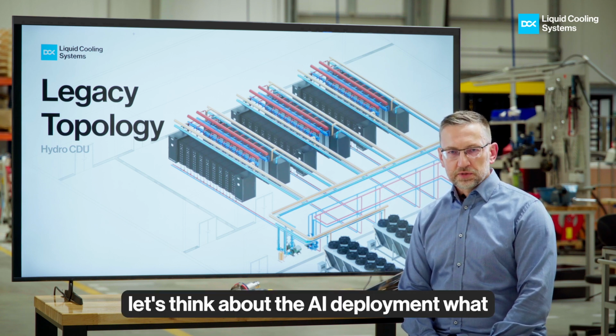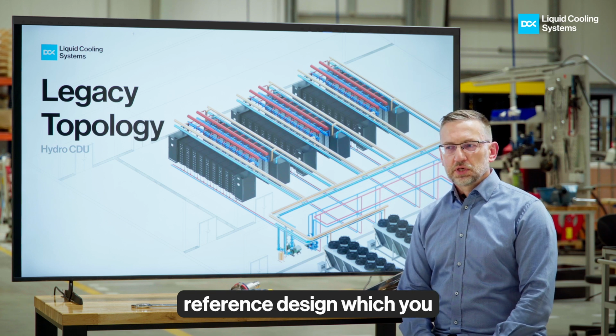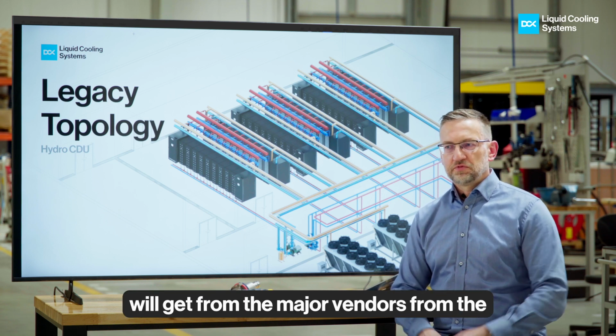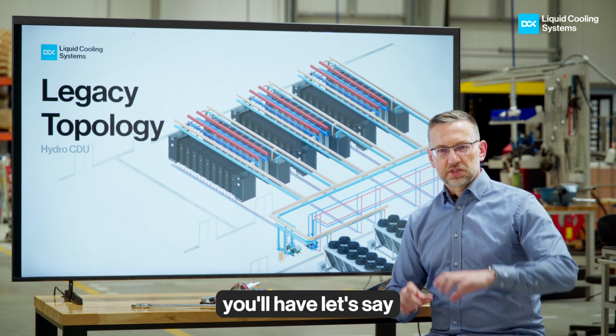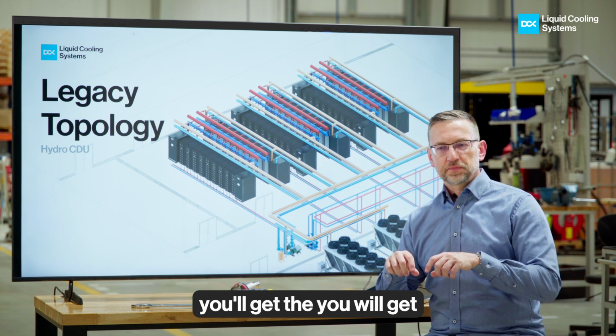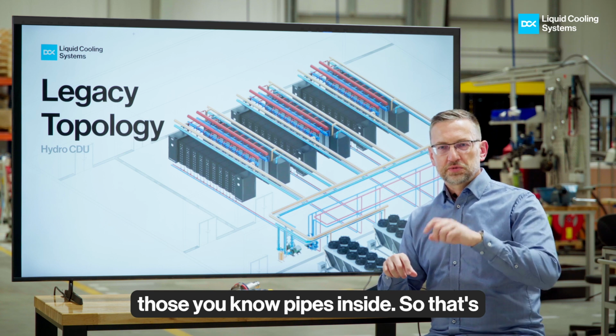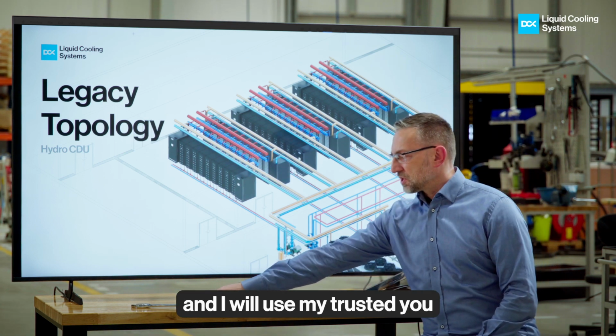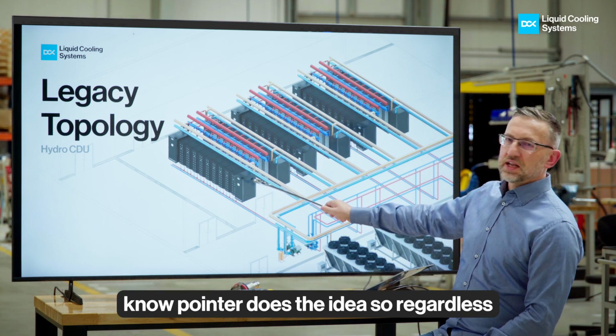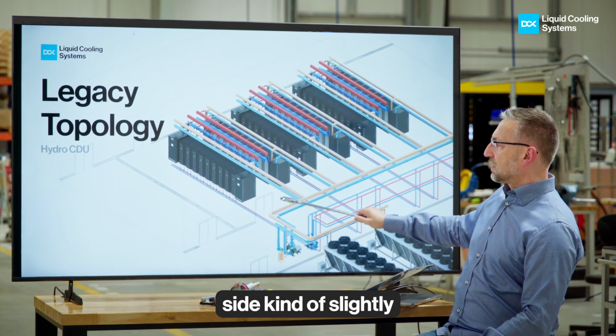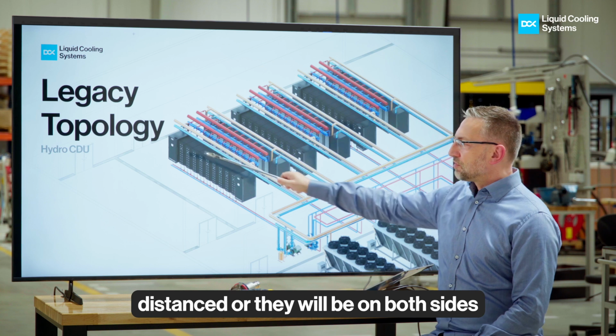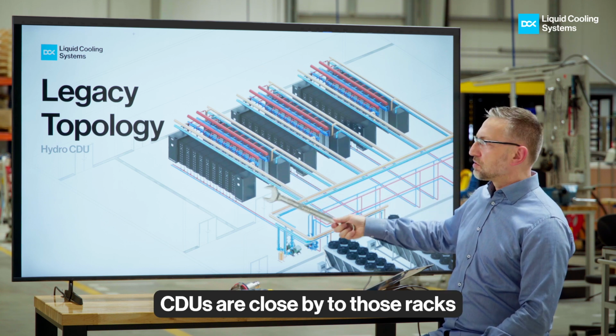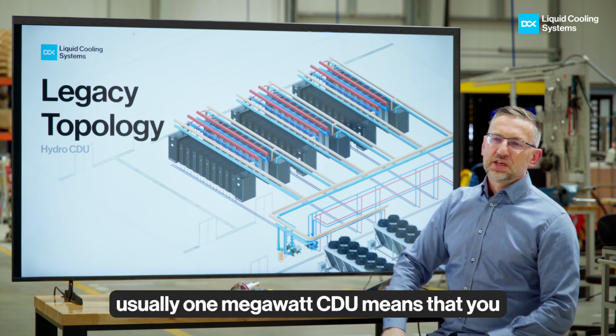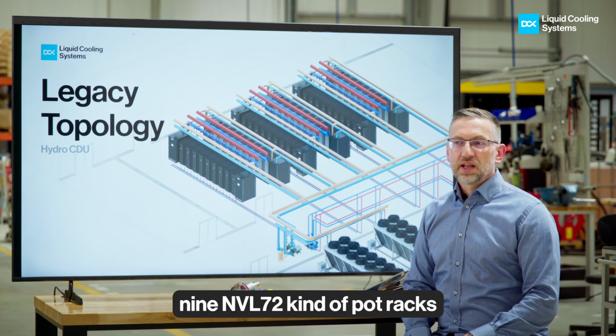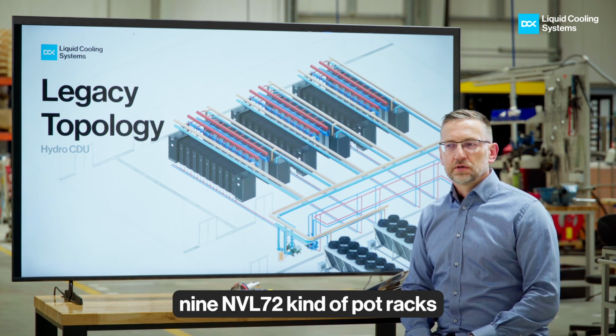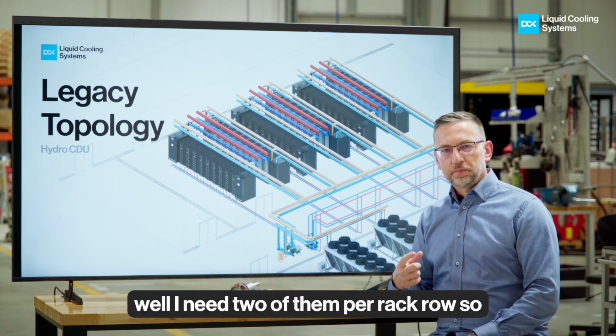So let's think about the AI deployment. In the typical reference design from the major vendors in the data center industry, you'll see that for a rack group, close by you'll get 2 CDUs and all those pipes inside. That's the example of such topology. Regardless whether the CDU is on one side, slightly distanced, or on both sides, it means that 1 megawatt CDUs are close by to those racks. Usually a 1 megawatt CDU can support about 9 NVL72 kind of pod racks, and you need 2 of them per rack row. So that's the generic topology, and you can see you need lots of CDUs.